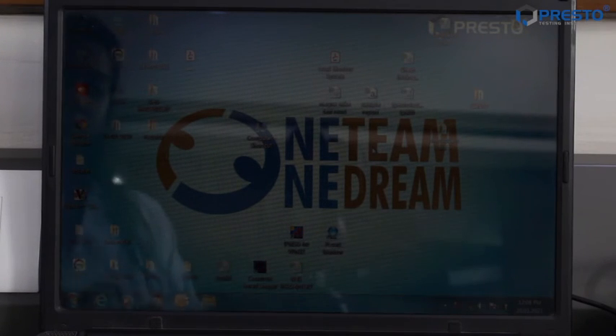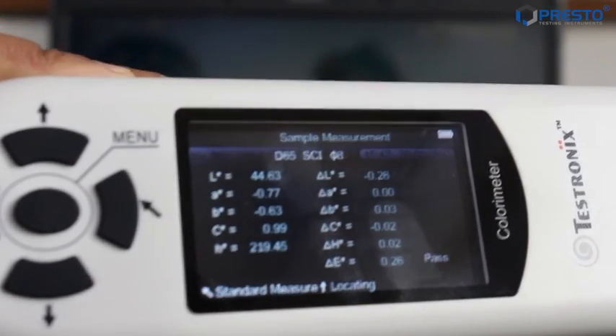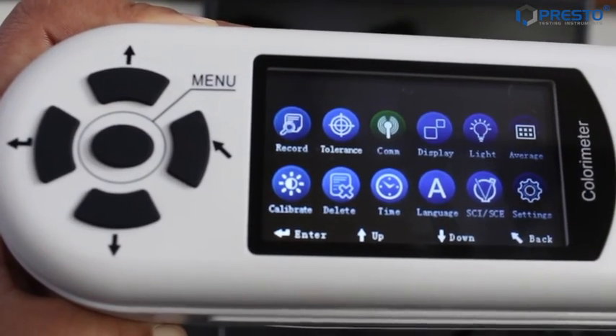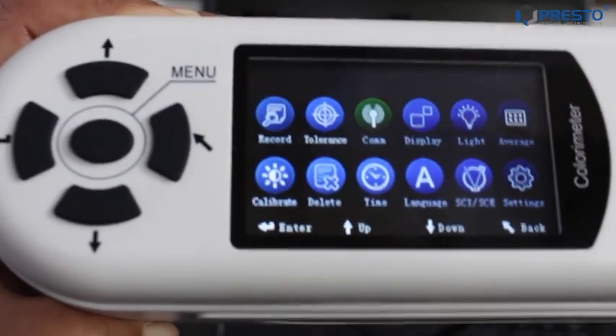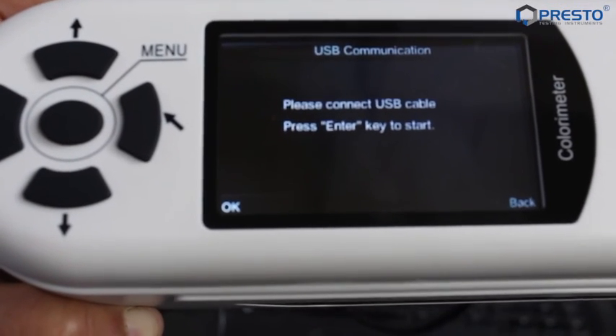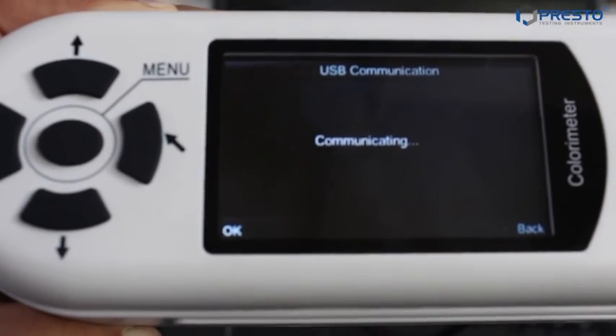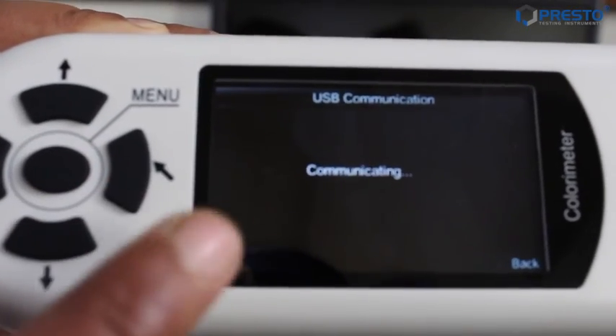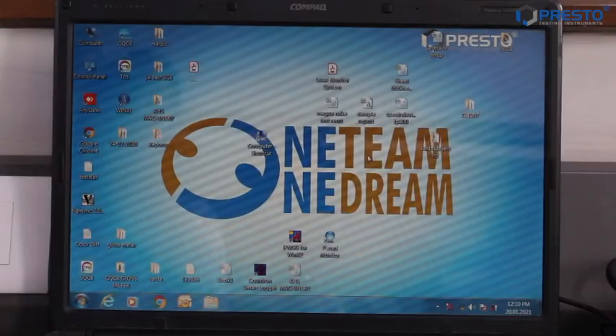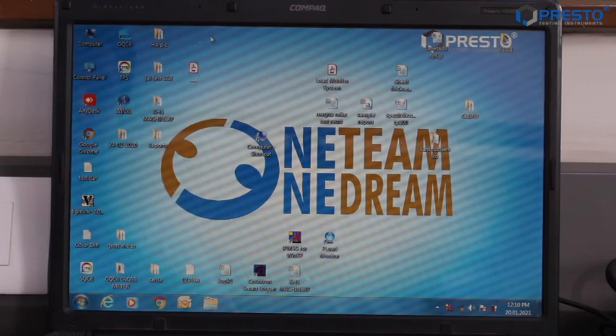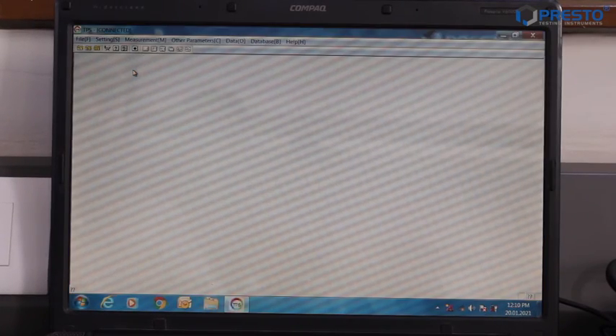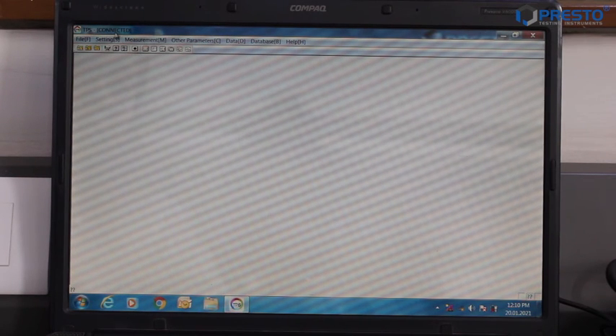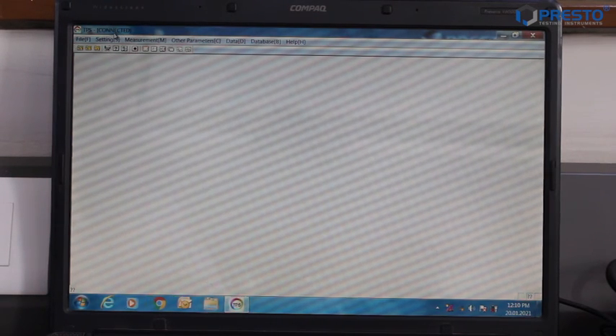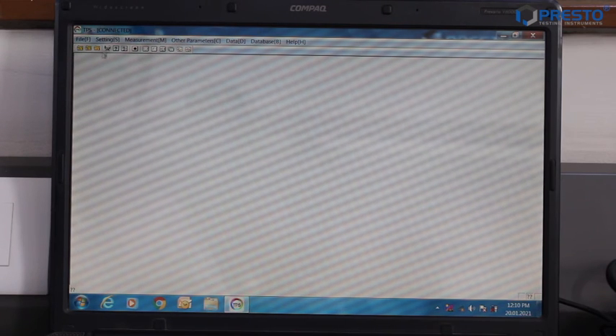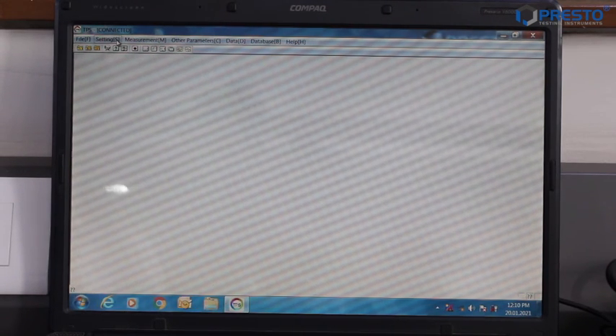Connect the instrument to the software, to the computer. Once the data cable is connected, go to menu, then click on COM, then again enter. So it shows it is communicating with the computer. Open the software. So the software is TPS. So this is the live status of the instrument. If it is not showing connected, then restart the instrument.